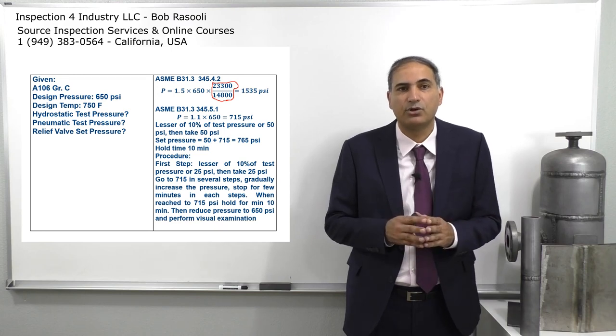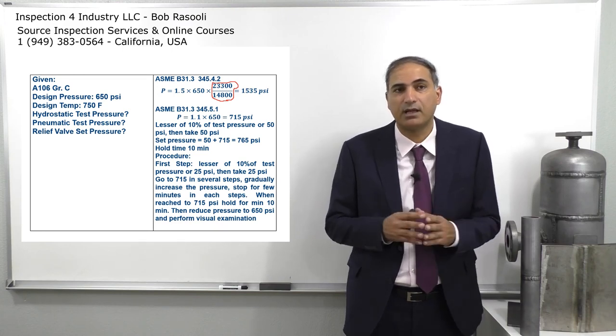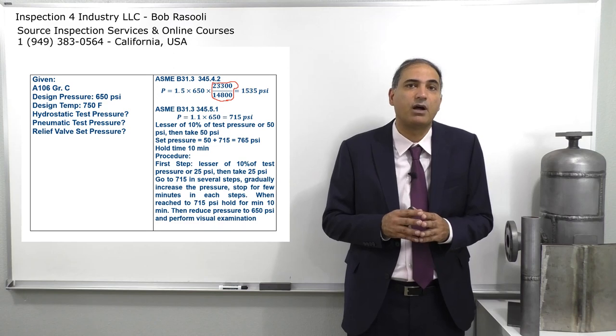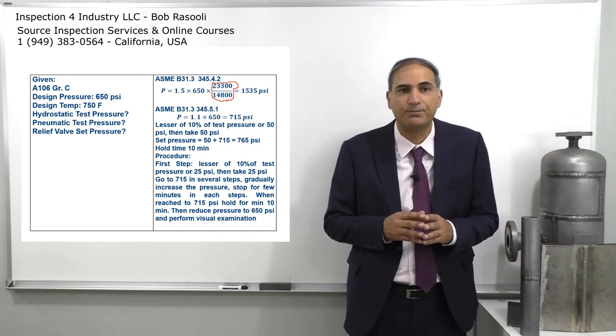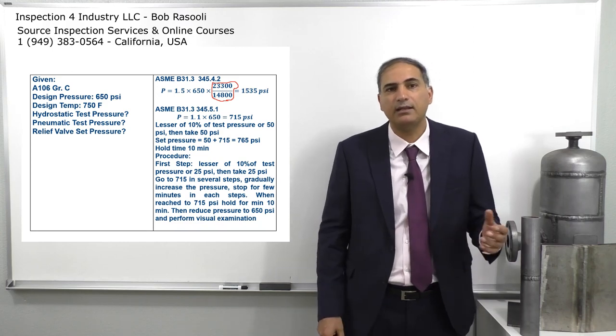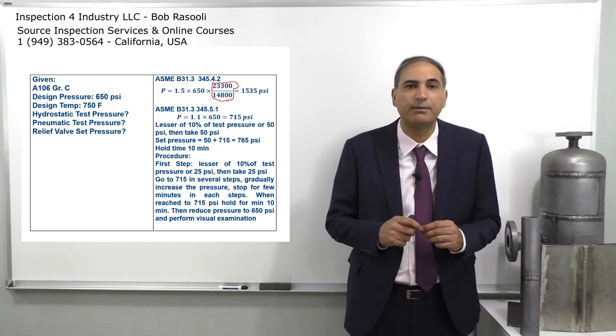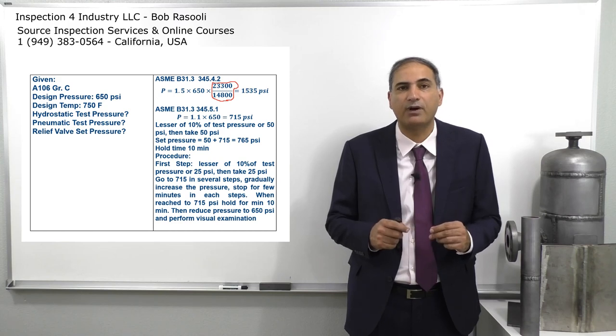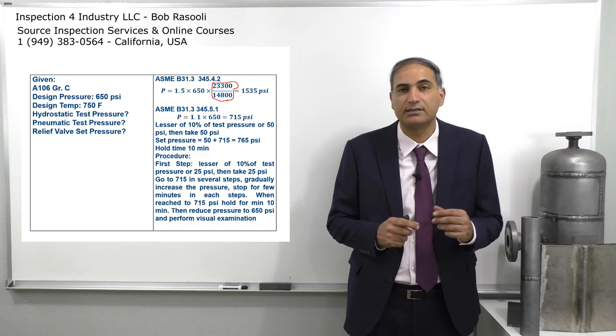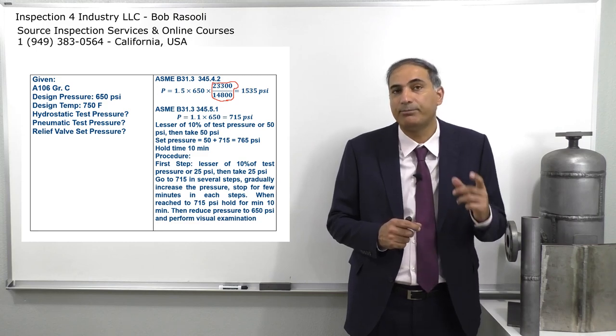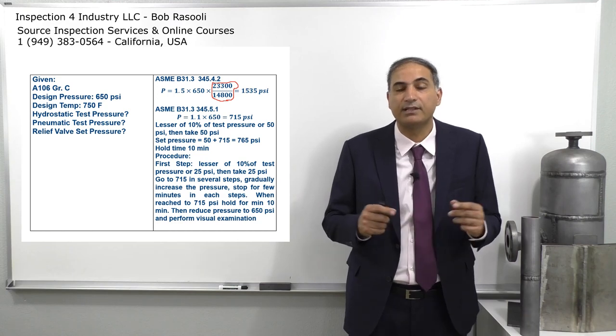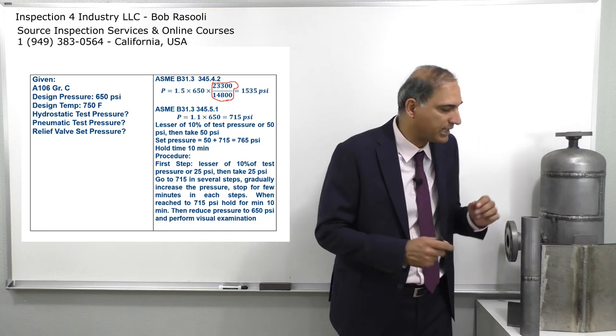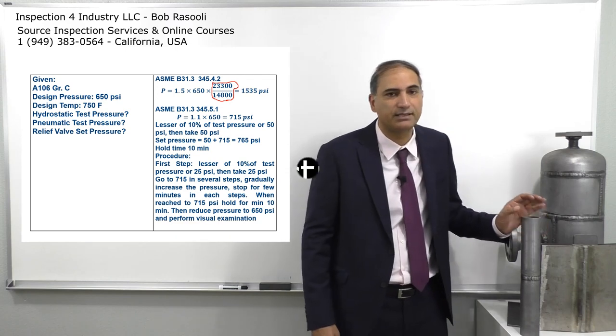The hold time is 10 minutes. For the first step, take the lesser of 10% of the test pressure or 25 psi. Ten percent of 715 is 71.5 psi, so 25 psi is less — we take 25 psi. Then we gradually increase to the full test pressure of 715 psi.